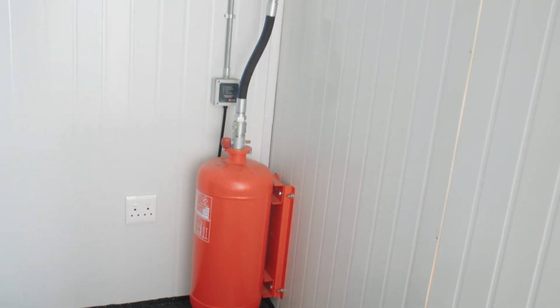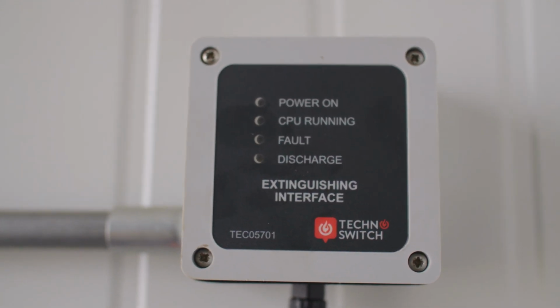We fit this into a container - this is a 40-foot container. In a 40-foot container, you can get about 2 megawatts worth of batteries. If you're going up to the 2 megawatt size, you'd put your inverters in a separate container altogether.